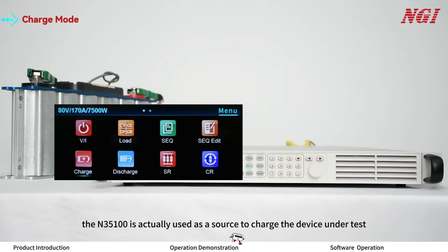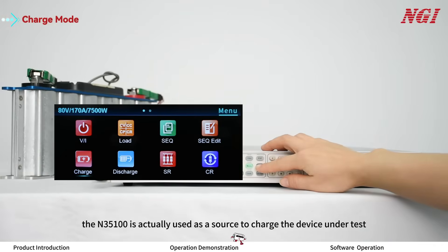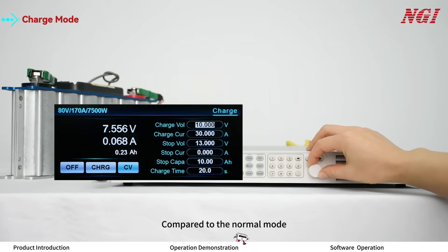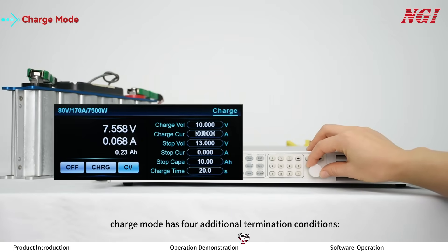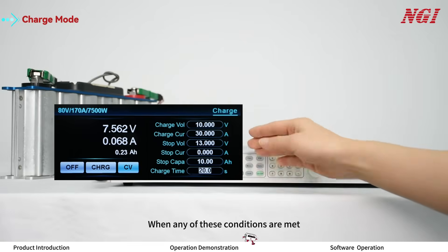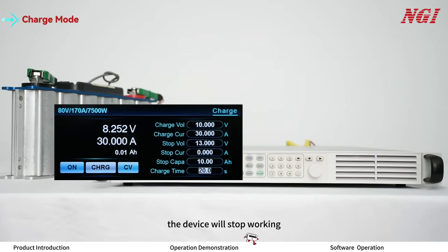In charge mode, the N35100 is used as a source to charge the device under test. Compared to normal mode, charge mode has four additional termination conditions: stop voltage, stop current, stop capacity, and charge time. When any of these conditions are met, the device will stop working.